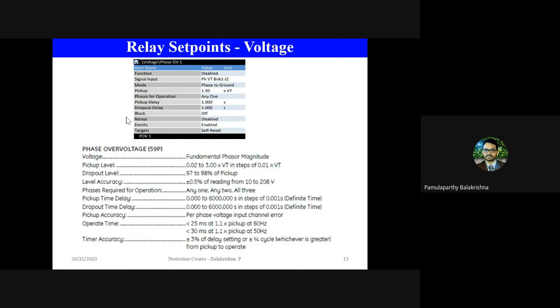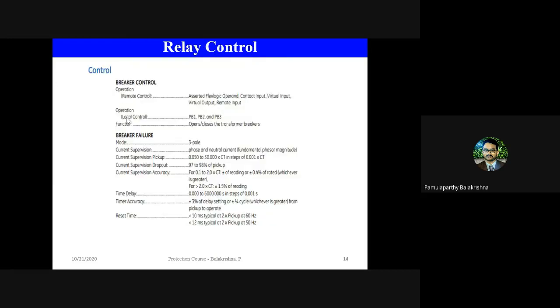Okay, so this is how the set points for each function work. I have just given you an example of current and voltage. Like that, there will be settings for frequency, power, differential protection, distance protection, whatever different protection functions you might have studied. All those protection functions require similar settings, either simpler or much more complex, that need to be done by the operator. Okay, so this is one of the very complex tasks that needs to be done when a relay is installed in the field, and it requires a lot of expertise to set this, because if you do anything wrong in the configuration, there is a chance that it can damage the asset, because the relay may not trip, and the transformer may even blast in the worst case. So that's why relay configuration is a very critical thing that is done in the substations.